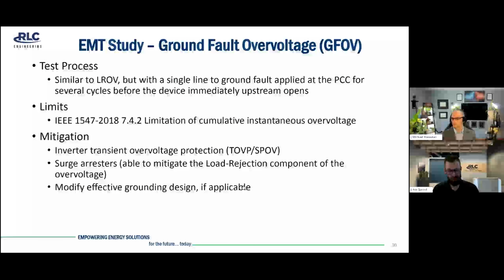So the second component of TROV is ground fault overvoltage, or GFOV. And this test process involves the same case posturing as LROV, but in this case, instead of a no-fault open of a protective device, we apply a single line to ground fault at the project point of common coupling, or PCC, for several cycles before the device immediately upstream opens. And we could make that assumption at this point in the study that that device would open because we would have already run coordination per Mike's discussion. Same limits, 1547, section 7.4.2. And the mitigation strategies, 2 out of 3 of these are the same thing. So inverter SPOV, either enabling or tweaking those settings, or surge arresters.